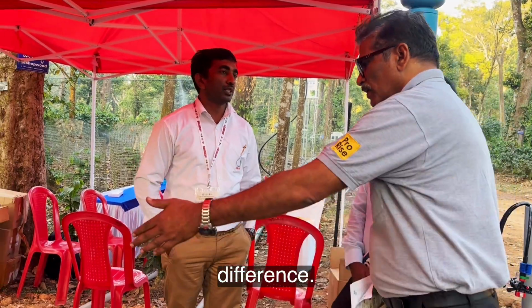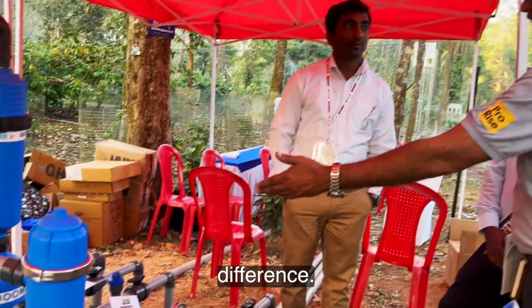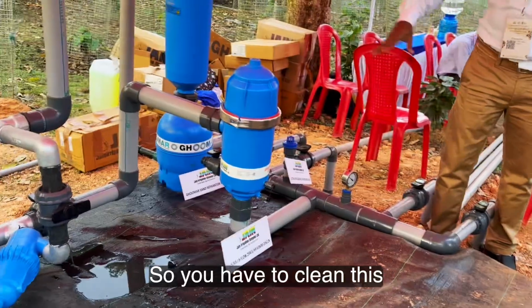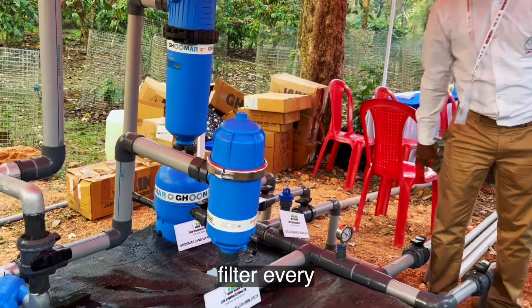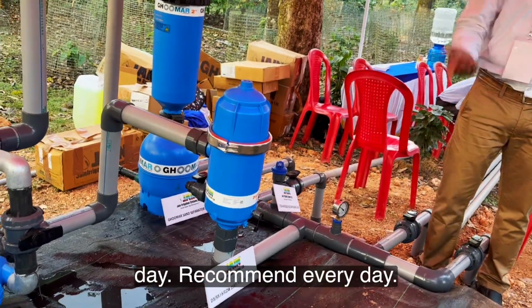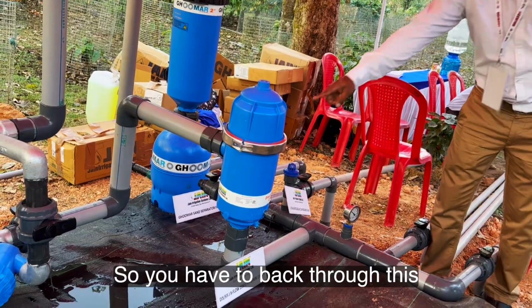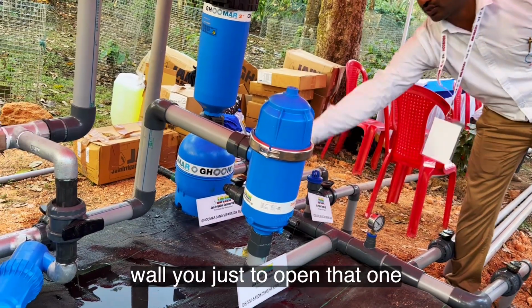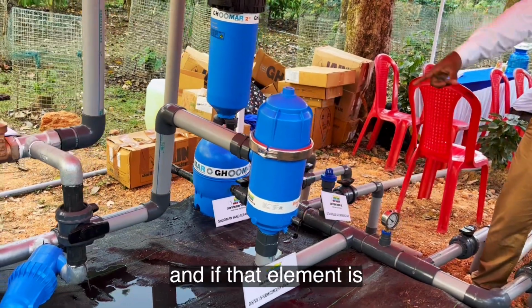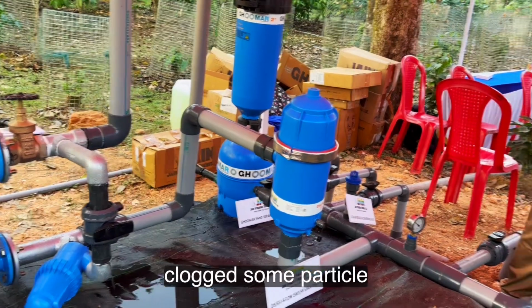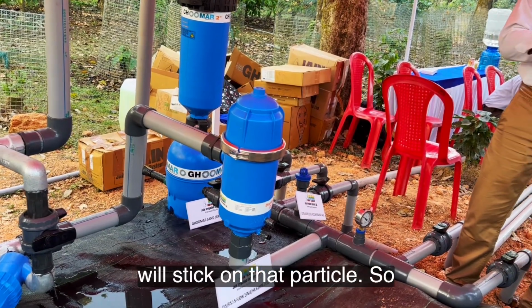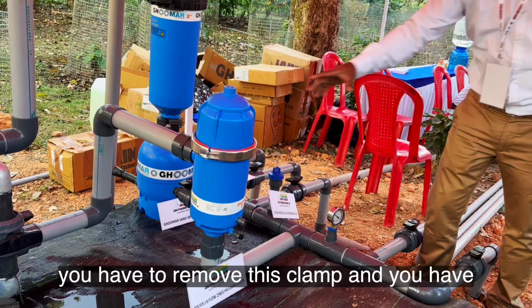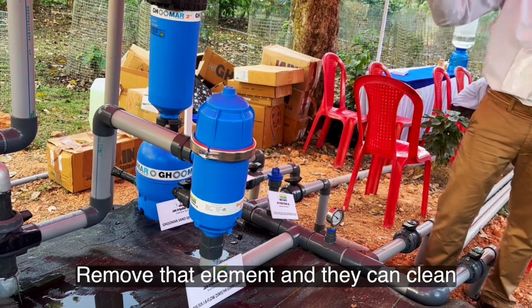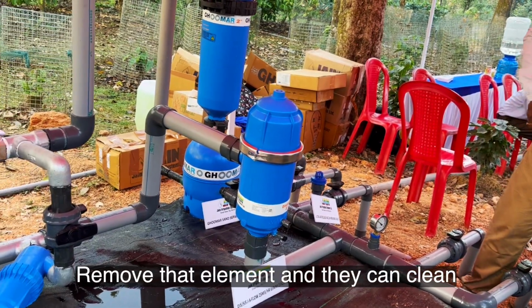How frequently should this be cleaned? You have to clean this filter every day. Recommended every day. You have to backwash through this valve. If the element is clogged, some particles will stick on it, so you have to remove this clamp, remove that element, and clean it.